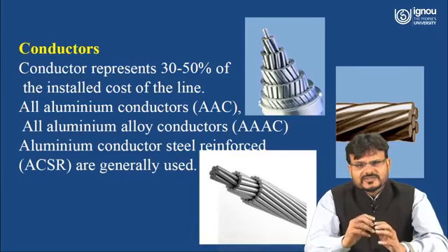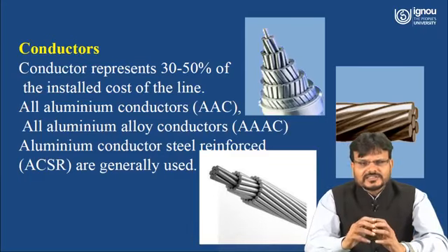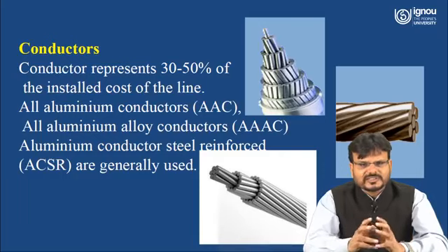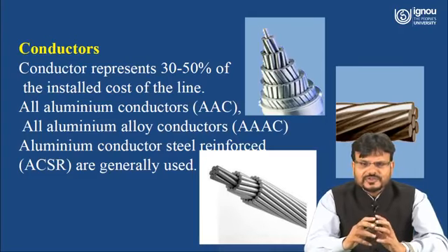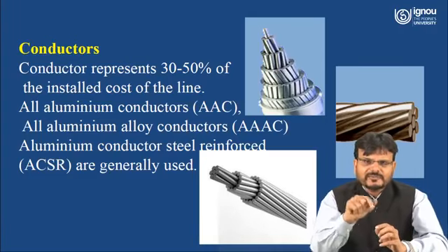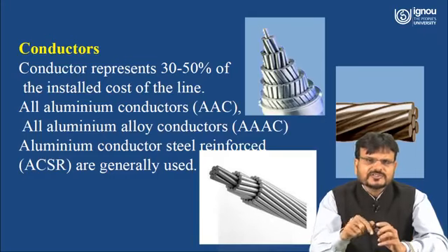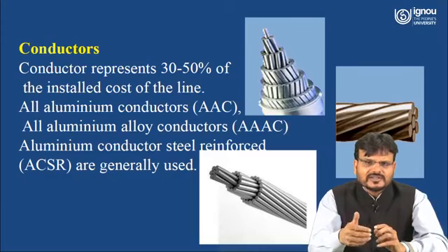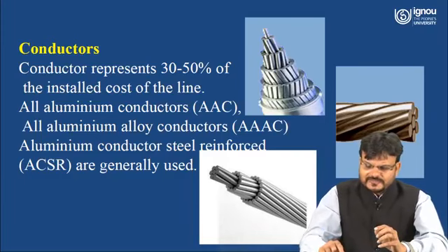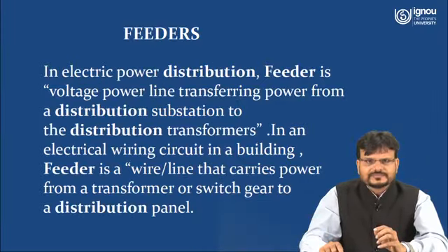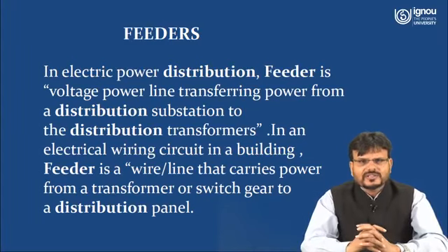Because in the case of AC supply, there is a tendency for the current to flow on the outer surface of the conductor. This type of effect is called skin effect. So here you can understand that in the middle portion of the conductor, current doesn't flow, so that middle part can be replaced by steel, which will support the conductor and increase the mechanical strength of the conductor.